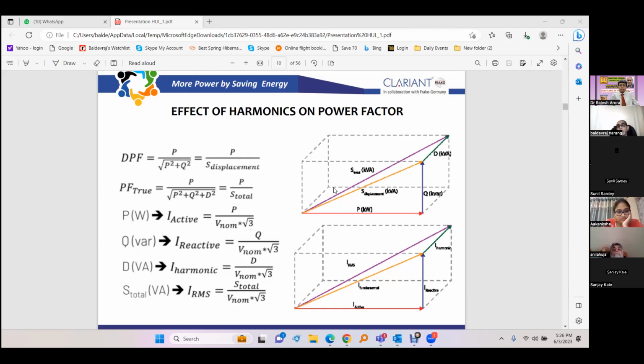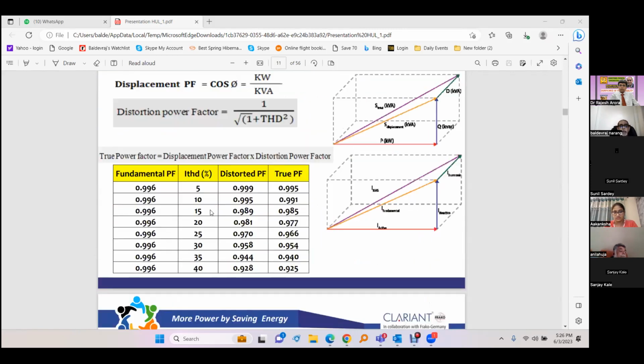And then people will have to see that the harmonics are also reduced. As it is, we have to take care of harmonics in a different way because of the IEEE 519 guidelines, and there are penalties being imposed. So in any case, we have to take care of the harmonics, whether the billing takes them into account or not. And this is the impact. Suppose you have a power factor of 0.996 initially, and you have THD of 5%, your true power factor reduces from 0.999 to 0.995. And as the value of ITHD goes up, the difference between the true power factor and the normal power factor becomes very high. Instead of 0.996 displacement power factor, it will become 0.925. There is a 0.07 decrease, and that will increase your bill by 7% if it is taken into account.